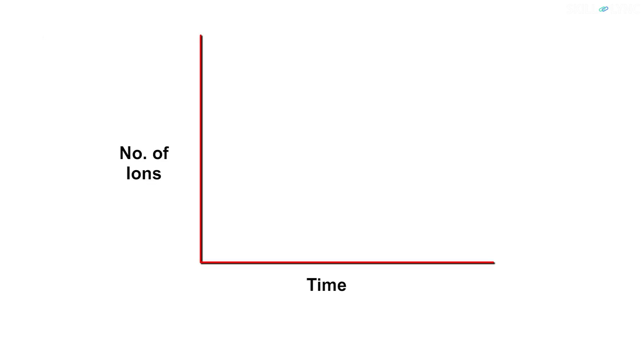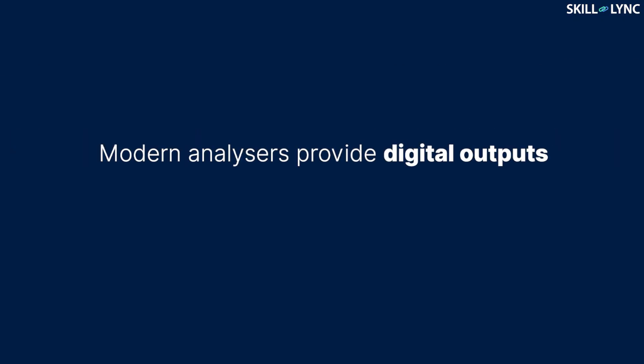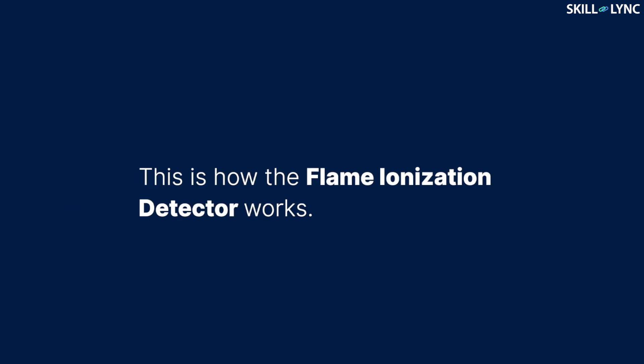The result will be in the form of a graph with time on the x-axis and the number of ions on the y-axis. Whenever the sample contains hydrocarbons, the carbon ionizes, resulting in an ionization current which is represented as a spike in the graph. Modern analyzers are capable of giving digital outputs. This is how the flame ionization detector works.